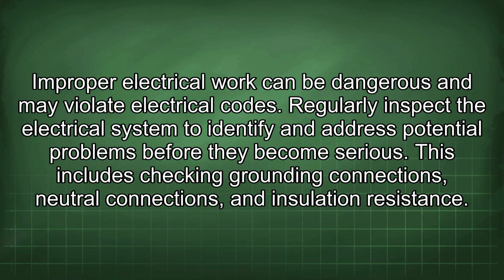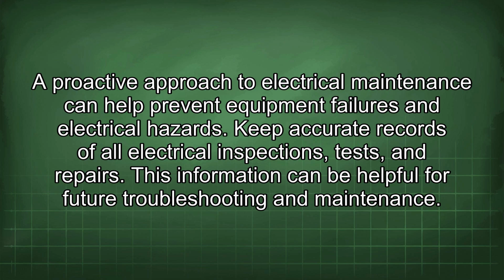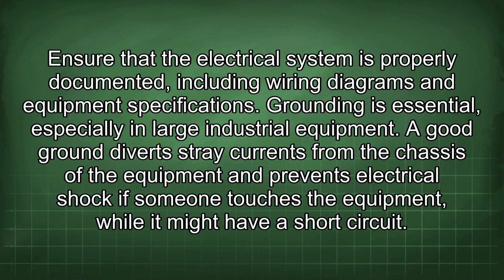Regularly inspect the electrical system to identify and address potential problems before they become serious. This includes checking grounding connections, neutral connections, and insulation resistance. A proactive approach to electrical maintenance can help prevent equipment failures and electrical hazards. Keep accurate records of all electrical inspections, tests, and repairs. This information can be helpful for future troubleshooting and maintenance. Ensure that the electrical system is properly documented, including wiring diagrams and equipment specifications. Grounding is essential, especially in large industrial equipment. A good ground diverts stray currents from the chassis of the equipment and prevents electrical shock if someone touches the equipment while it might have a short circuit.